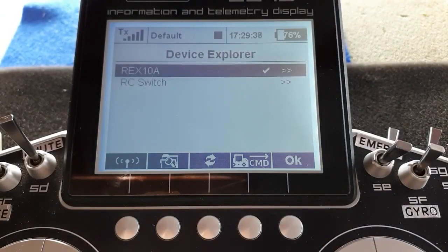Now, you can actually think about going ahead and using it, but we're coming up to 10 minutes in this video, so I'll stop there and we'll make an episode 2 covering further stuff to do. But at least now you know it's bang up to date, it's got the best software on it, and it's been calibrated, it's properly ready to use. Imagine you hadn't done that calibration, it was a little bit on edge, and once you've got it double-sided taped into the model, it then comes up with the error message, sensor calibration required, or whatever it is. There is an error message that says it needs calibrating, and that's a damn sight harder to do once it's taped deep inside the model.